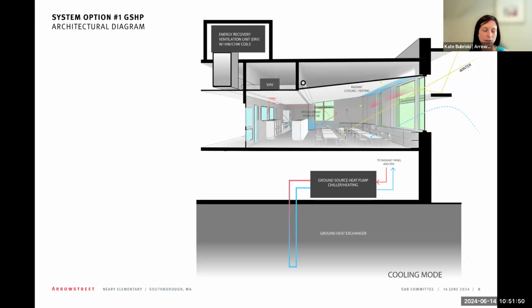Yeah, we typically estimate that the well will be between 1 and 2 tons. 2 is on the high side. Usually we don't get quite to 2. It's usually between 1 and 1.5 tons per well. So if you have 50 tons of cooling, and as a perspective of what that looks like, 40 wells would be roughly a site space of like 40 by 100 feet.